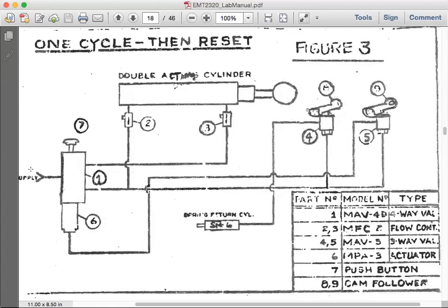Okay, so that's what you have. The initial stage is when the piston is inside. Since the piston is inside, and you know that from supply, the stem originally is up. If the stem is up, the pressure from the supply goes where the stem is. So it goes through the top, comes right here, and fills up the front, the right chamber of the cylinder, keeping the piston inside.